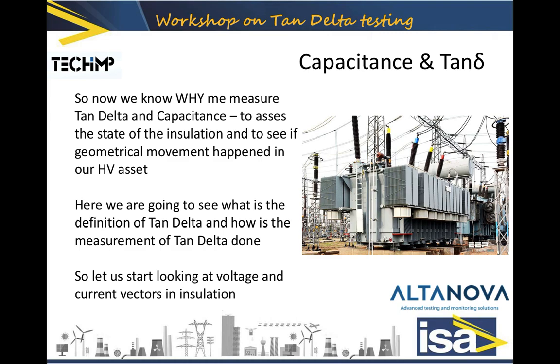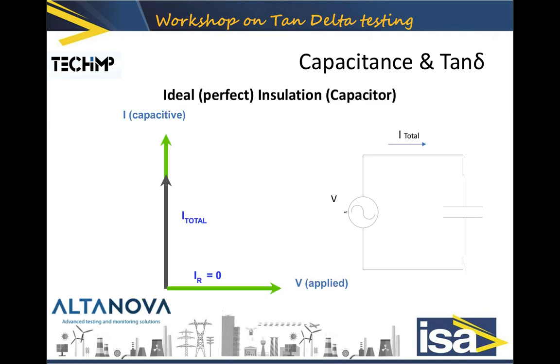We are going to see what the definition of tan delta is and how the measurement of tan delta is done. In a perfect insulator — a perfect capacitor — we have a simple situation with an AC source and our ideal capacitor, which is defined by the fact that the voltage applied on it and the current are 90 degrees apart, with current leading by exactly 90 degrees.